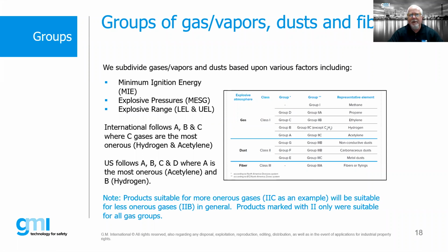Okay, no worries. Great. So a little bit further about our wall chart. Within gas and dust, we now need to subdivide these gases and dust. And we base that upon a couple of factors: the minimum ignition energy, the MIE, the explosive pressures, the MESG, and the explosive ranges of various gases. The LEL is the lower explosive limit, and UEL is the upper explosive limit. MIE comes into play specifically when we're selecting intrinsically safe barriers. That's the minimal amount of energy that it takes to ignite a flammable gas air mixture.